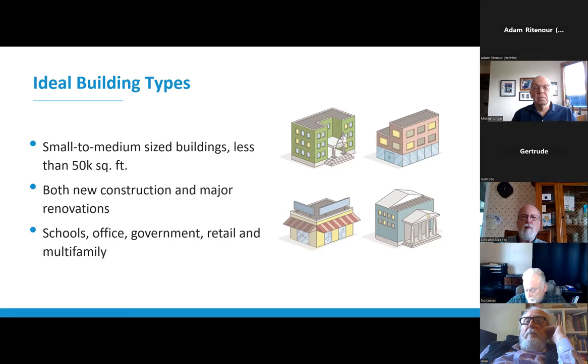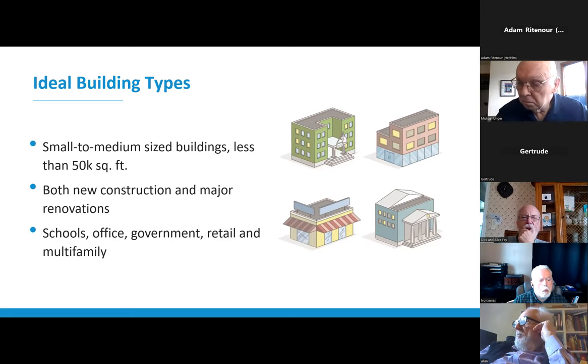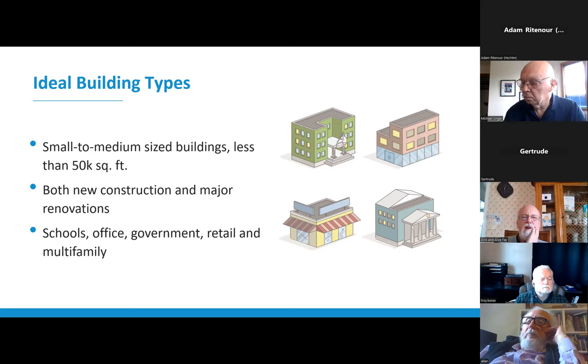In an existing building, this VHE DOAS system replaces conventional simple HVAC equipment like RTUs through a system conversion. And in new construction, it's actually included in the planning and design process from the outset. There are other buildings like restaurants, hospitals, and warehouses that can use VHE DOAS, but they're less ideal for this application, at least for NIA's purposes, and they're not NIA's target building type, mainly because it requires much more careful analysis and design to be effective. Not that those buildings can't save energy with VHE DOAS, it's just a little trickier to get the design right.